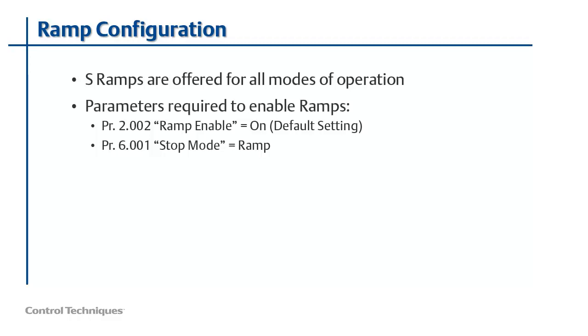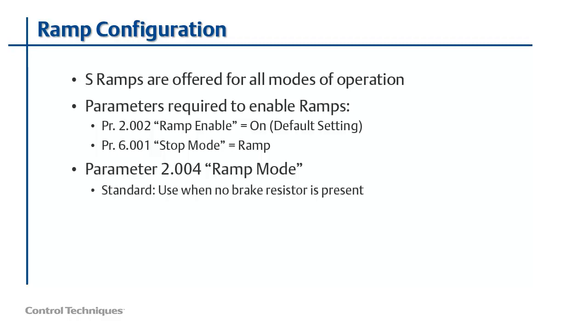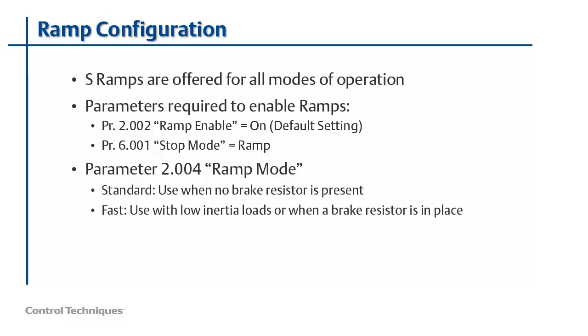There are also two options for how ramps are used in the drive. Parameter 2.004 is called ramp mode, and the choices are either standard, which is the default setting, or fast. In standard mode, the drive will automatically adjust the slope of the deceleration ramp to ensure that the energy that is produced by the motor during deceleration does not adversely affect the DC bus in the drive and cause it to trip on an overvoltage trip. In fast mode, the drive will always honor your programmed acceleration and deceleration rates. If you are driving a load with high inertia, such as a solid nip roller or a winder for example, this mode may not work for you unless you use a dynamic braking resistor to help dissipate the energy that is produced during deceleration.